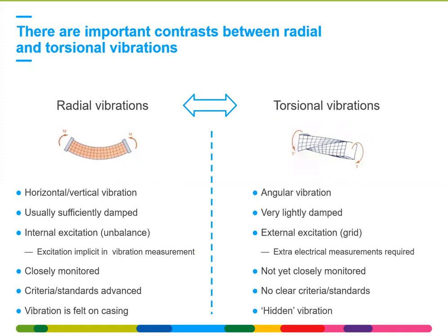You connect your power plant to the grid. If you don't know what happens in the grid, then you could have a potential interaction. And the issue is that it's not yet closely monitored. You do not have, by default, torsional vibration monitoring on your shaft line, so you're actually blind to whatever potential interaction with the grid may be. There are no clear criteria and standards; we'll come back to that later. And it's a hidden vibration.